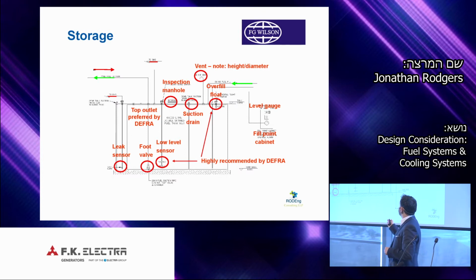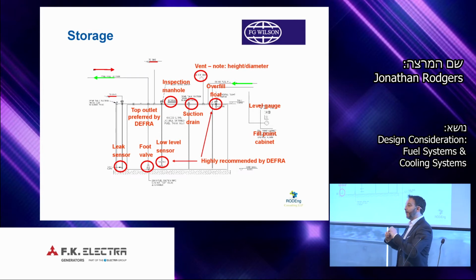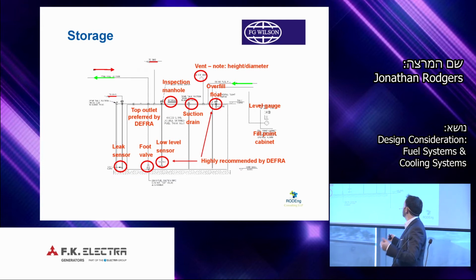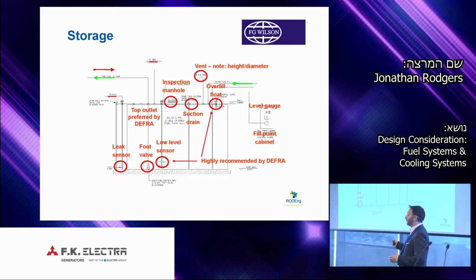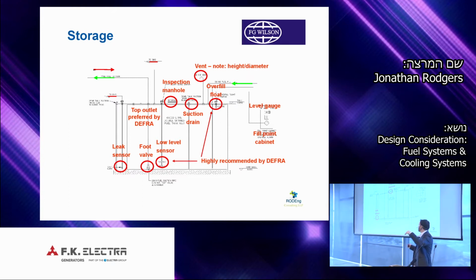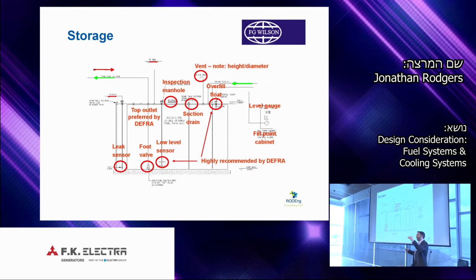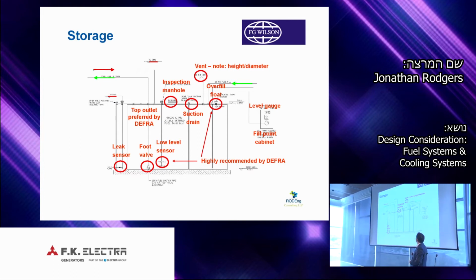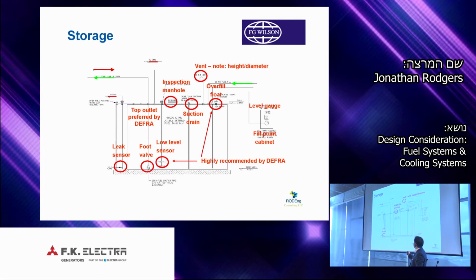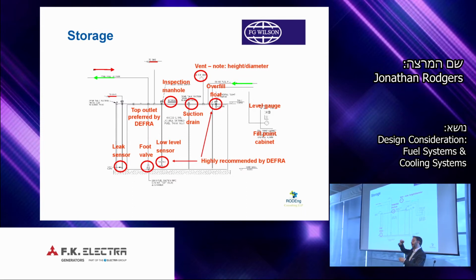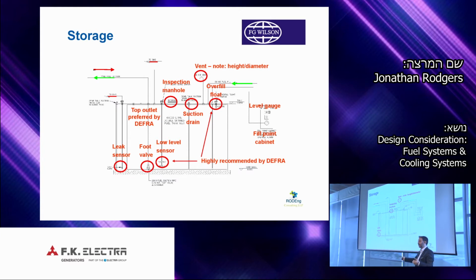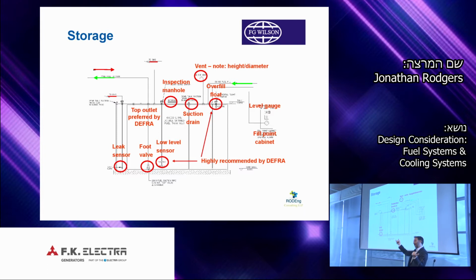We've our fill line, so we need to size our fill line. And we size our fuel suction lines, so the sizes of the pipe, and that's relative to the pressure within the tank for supply and for extract. We may have a fuel return if the fuel is returning from an engine, or it could be a fuel dump from a day tank to a bulk tank. Each of these have to be sized with the sizing of the vent from the top of the tank, because as fuel goes into the tank, air must escape. As fuel leaves the tank, air must come in.